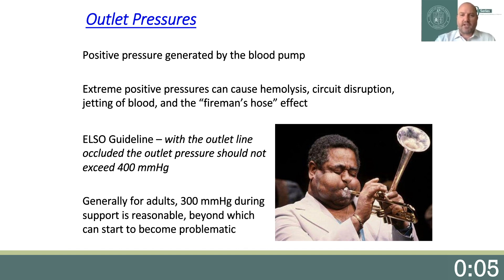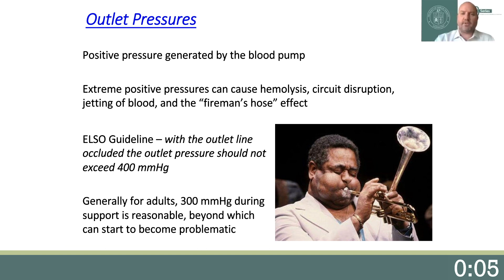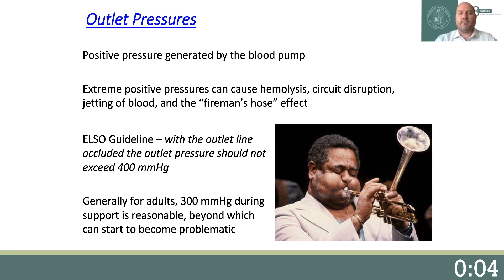Similar to venous inflow pressure, identifying abnormal circuit outflow pressures or pressure trending and the clinical consequences is also important. Outflow pressures are positive pressures generated by the blood pump. Extreme positive pressures can cause hemolysis, circuit disruption, jetting of the blood, and the fireman's hose effect, where the cannula tends to want to pull out of the patient with higher pressure generation. ELSO guidelines state that with the outlet line occluded, the outlet pressure should not exceed 400 mmHg. This can be accomplished by limiting pump speed or by servoregulation. Generally for adults, most would agree that 300 mmHg during support is reasonable, beyond which it can start to become problematic.